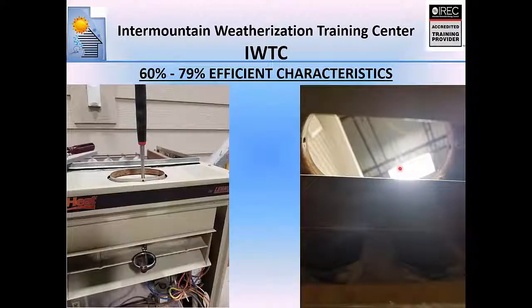So here's that draft diverter or draft hood that we talked about. I took my inspection mirror, took the flue off, and I can stick that right down through. It's a direct connection right into the house, or the envelope, if you will. Here's a picture looking up through it, and you can see each burner compartment. So all the flue gases come out of here into the draft hood, and hopefully the flue's working right, and they all go up and out.